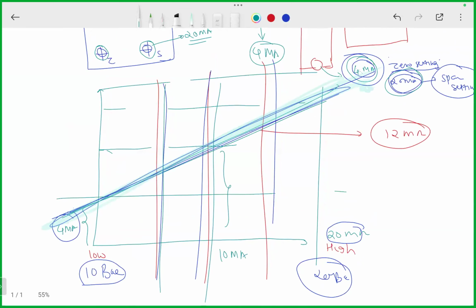This is your 0% opening and this is your 100% opening. So let's say my output signal is 10 milliamp - I will check on this 10 milliamp line how much the valve is open. Yes, maybe 30% it is open. Understood? So a lot of things can be done by plotting this graph.